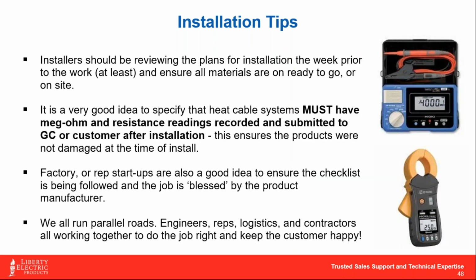If the cable goes in with full structural integrity and isn't damaged, it's going to work for years, trouble-free. The way you check that is to measure it with a megger, shown in the upper right-hand corner in that blue square. It works like a multimeter—you put one probe on a bus wire, the other probe to ground, push a button, and it tells you whether it's good or bad. It can give a numeric readout, and we actually have ones that flash a red light if it's bad, so it makes it obvious.